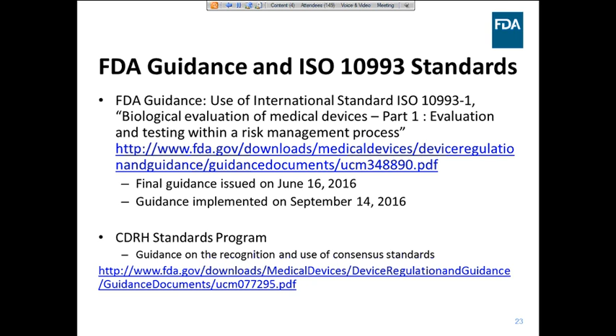So as I mentioned earlier, ISO 10993 Part 1 describes device categorization. So for biocompatibility assessment, the devices are categorized based on nature of tissue contact and duration of tissue contact. Based on the nature of tissue contact, the devices are categorized as surface contacting device, external communicating device, and implant device.